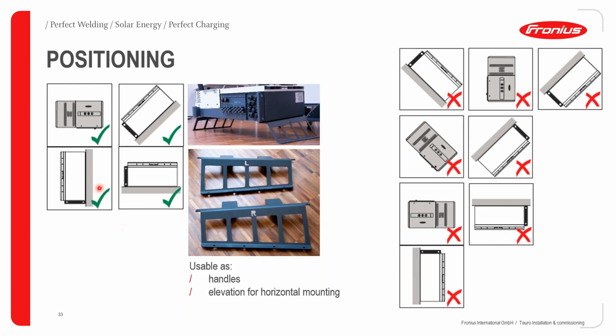And this will pretty much explain each orientation that is allowed and each orientation that is not allowed. Another reason for the allowed orientations versus the disallowed is the topic of active cooling. With the Tauro, we've got a fan that pulls in air from the slot over there, and then it passes out hot air from the sides of the inverter. And as you also know, hot air rises as well. So all these combinations are allowed.